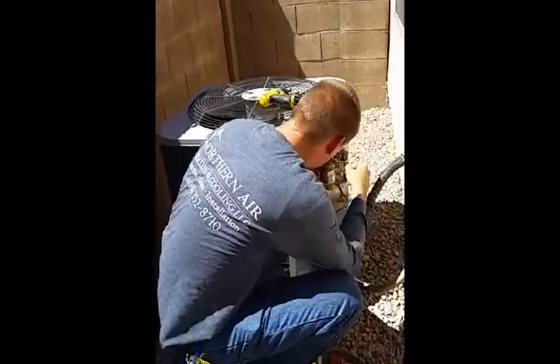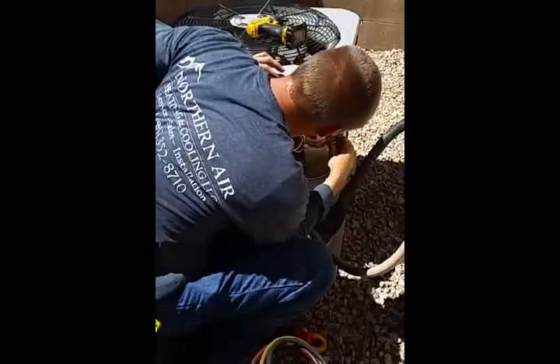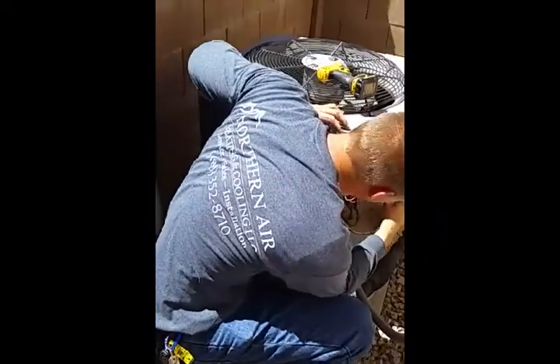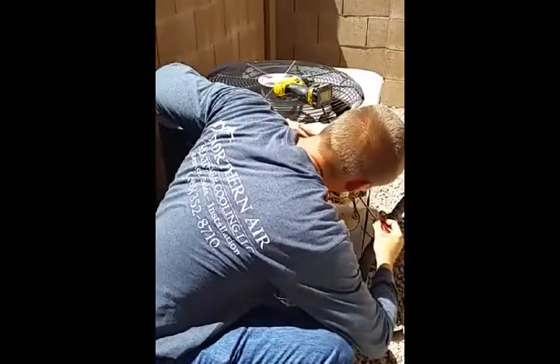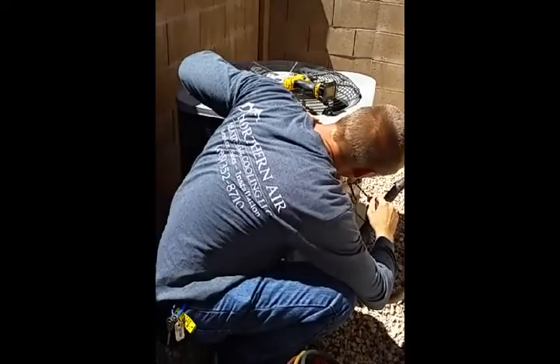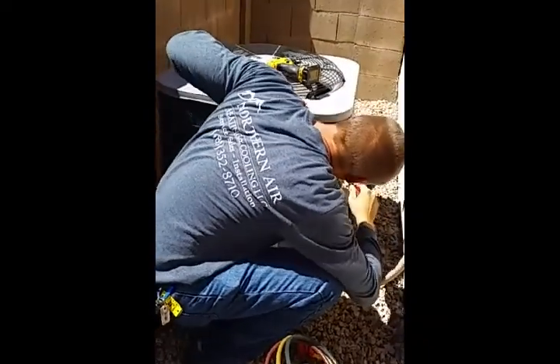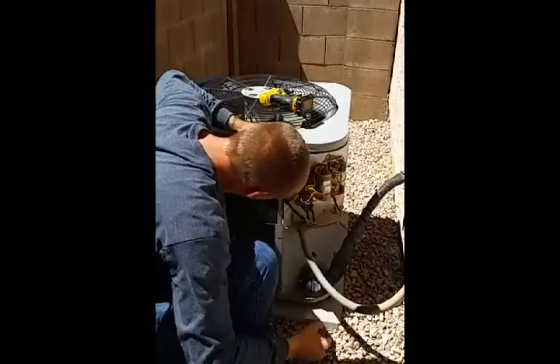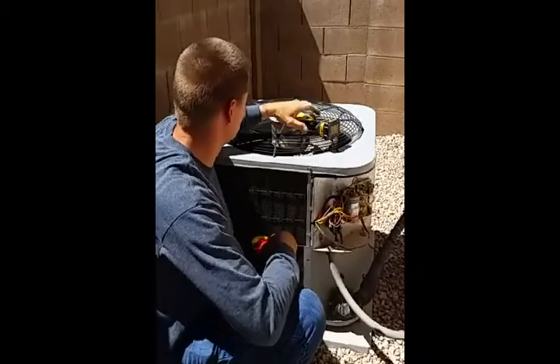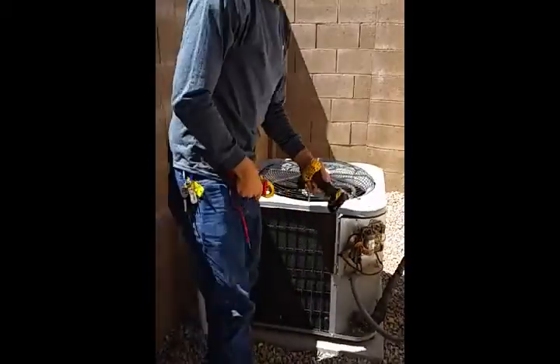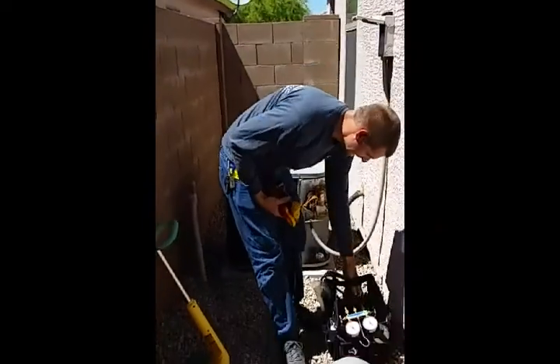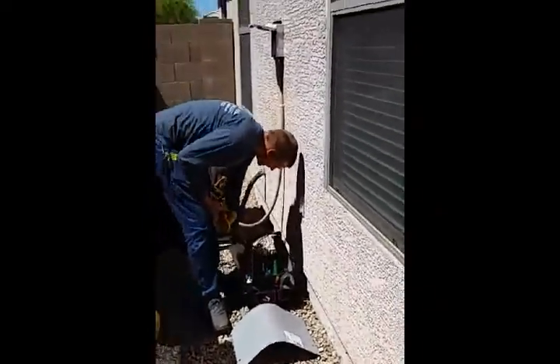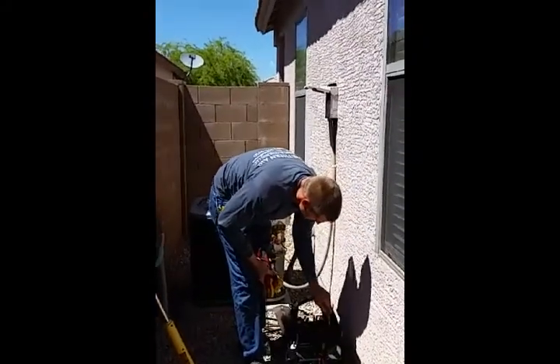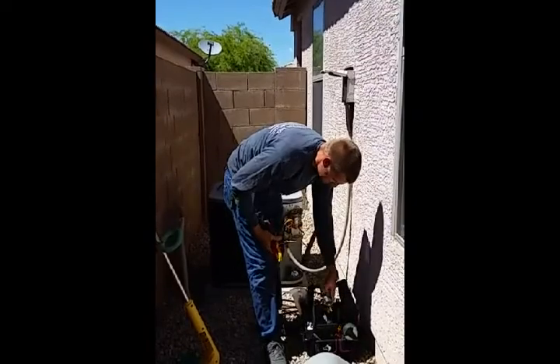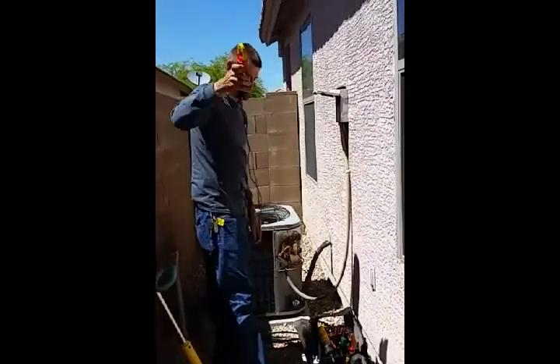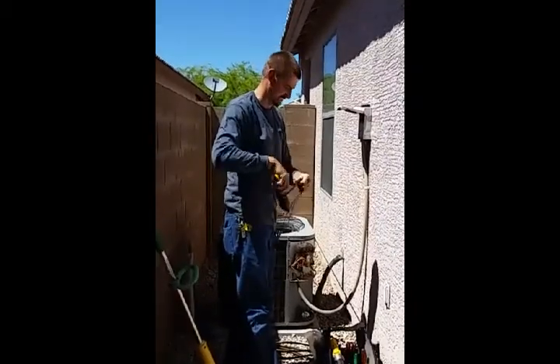Okay, again, all the electrical connections are tight. Get an inspection overall of all the electrical components in the system. Everything looks good. Okay. Now, what we want to do is go upstairs into the attic. Our air handler is in the attic on this house. So we will go up into the attic and test out the connections, capacitors, and make sure all the connections are also tight as well as the disconnect.